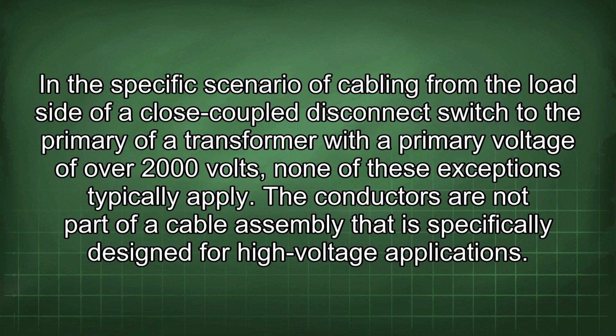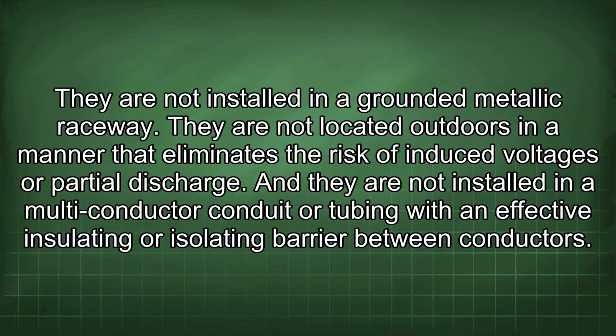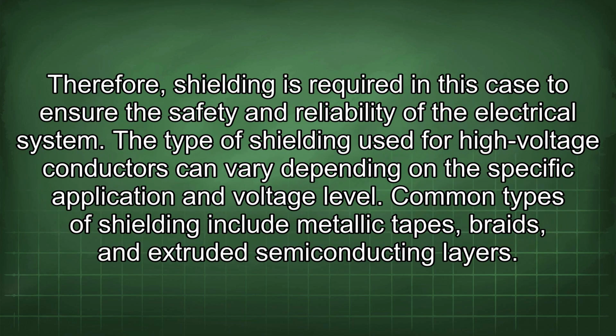In this specific scenario of cabling from the load side of a close-coupled disconnect switch to the primary of a transformer with a primary voltage of over 2000 volts, none of these exceptions typically apply. The conductors are not part of a cable assembly that is specifically designed for high-voltage applications. They are not installed in a grounded metallic raceway. They are not located outdoors in a manner that eliminates the risk of induced voltages or partial discharge. And they are not installed in a multi-conductor conduit or tubing with an effective insulating or isolating barrier between conductors. Therefore, shielding is required in this case to ensure the safety and reliability of the electrical system.